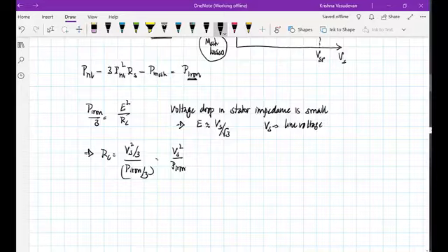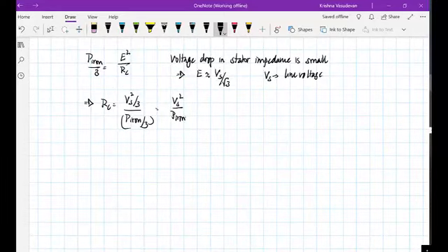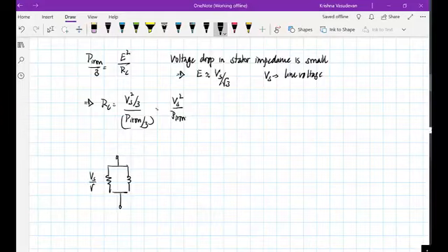Now having got this value of RC, we know that you have RC and XM, and the voltage that is appearing here is Vs by root 3. So the flow of current in the resistance, IRC, is then given by Vs by root 3 divided by RC. You know the total current that is flowing in here because you have measured it, and let us say this current is I no load.